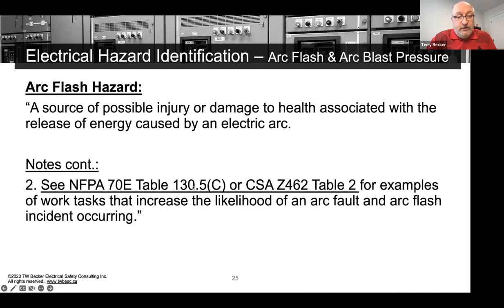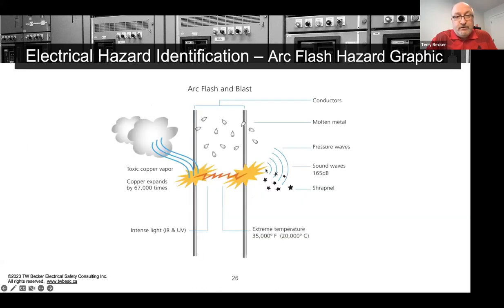All right. In the notes to the definition in 70E and Z462, it quotes those task tables I mentioned. So the two task tables that you can reference for a list, and it says likelihood of occurrence of basically an abnormal arcing fault as yes or no, based on condition of maintenance, right? And again, in some cases, normal and abnormal. And if we have normal operating or normal equipment conditions, we don't need arc flash PPE. So here's the graphic, the visual. Again, we get that voltage, three phase, right? We sustain this arc when we compromise that gap, and three phases interact instantaneously, and we get that arc flash.